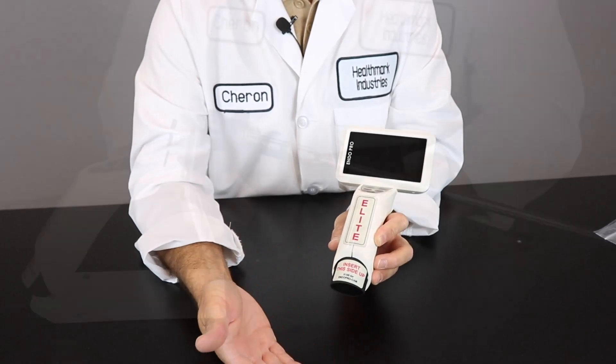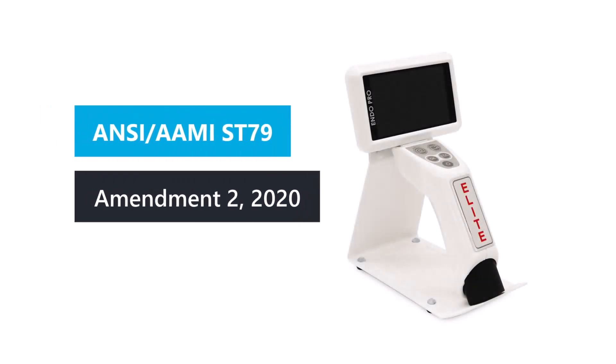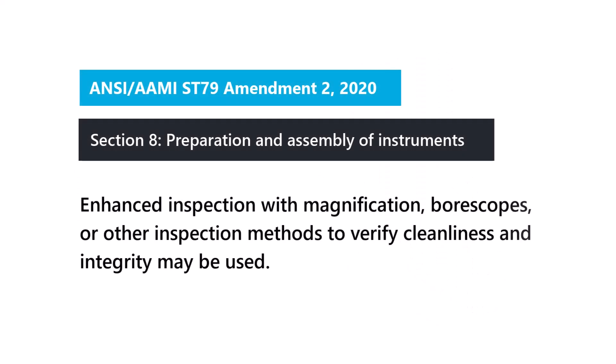Designed for evaluating the condition of rigid, semi-rigid, and flexible endoscopes without lumens, the EndoProCam acts as a portable video tower, and it can be used as a proactive approach to inspecting for damage and debris. The EndoProCam can help you meet the ANSI/AAMI ST79 Amendment 2, which states enhanced inspection with magnification, bore scopes, or other inspection methods to verify the cleanliness and integrity may be used.